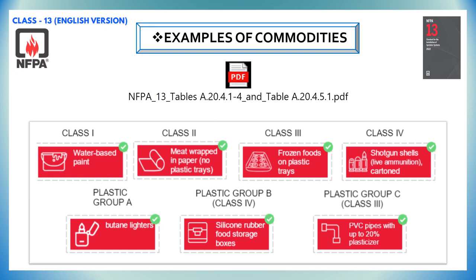For example, water-based paint comes under class 1 classification. Meat wrapped in paper with no plastic trays involved is class 2. Frozen food on plastic trays comes under class 3. Shotgun shells carton comes under class 4. Group A plastics — butane lighters, silicone rubber food storage boxes — come under group B plastic or class 4 commodity. PVC pipes with up to 20% plasticizer come under class 3 type or group C plastic type. All these can be found in NFPA 13 tables as shown on the screen.